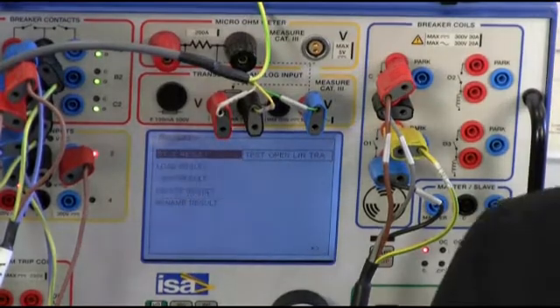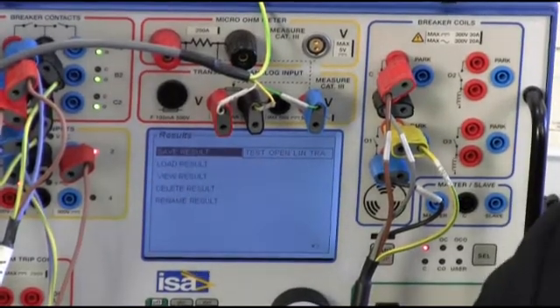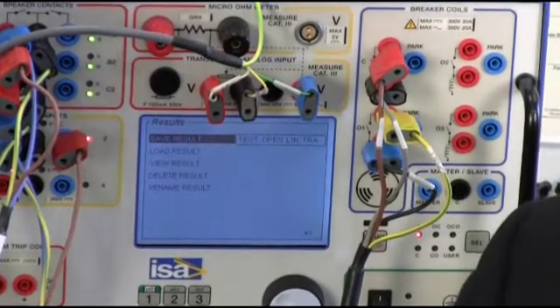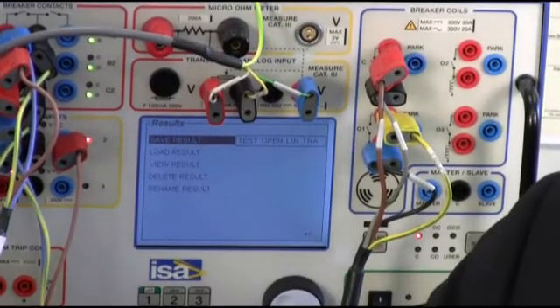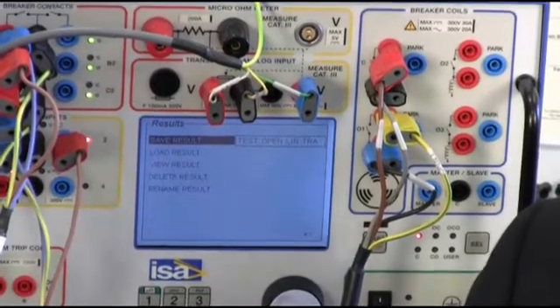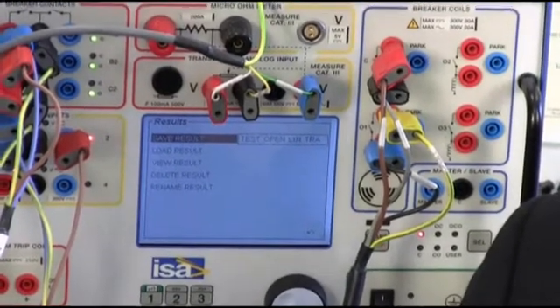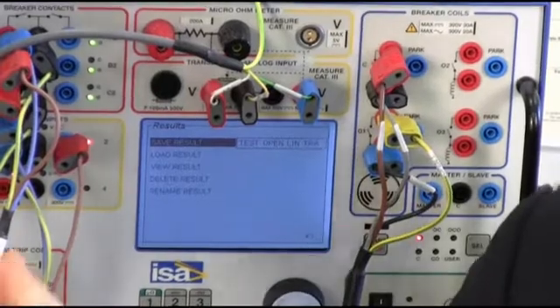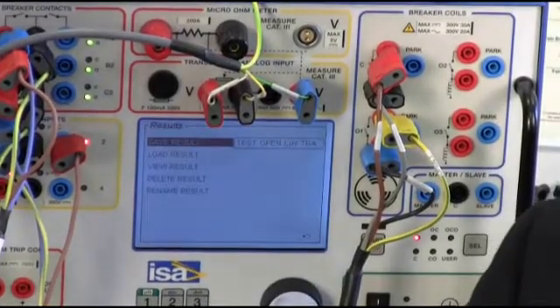And that's it. Of course, this test has to be repeated for the close command. And if you have, as in our instance, if you have mounted three transducers, one for each phase, you have to repeat the open and close transducer movement on the three phases.